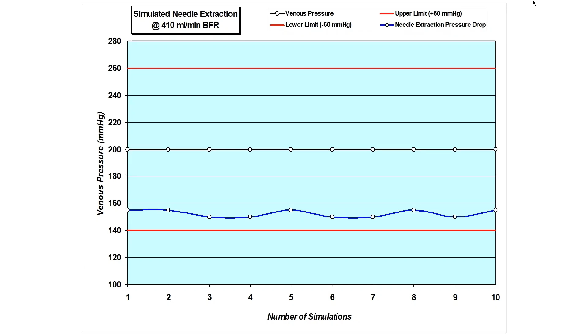So make sure that when you do set your venous limits, you restrict them as much as you can. Why do we set it at the widest spread? It's less alarms. We don't want to deal with the alarms, but it's not the safest methodology. Make sure you restrict it as much as you can so that this does not happen.